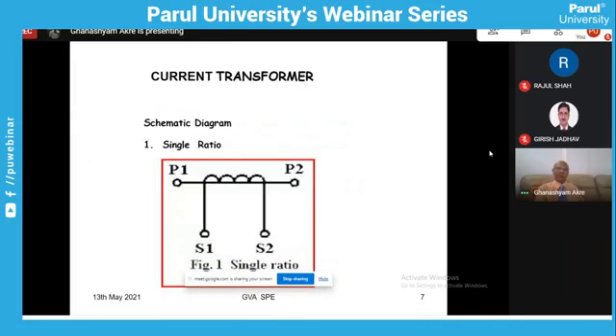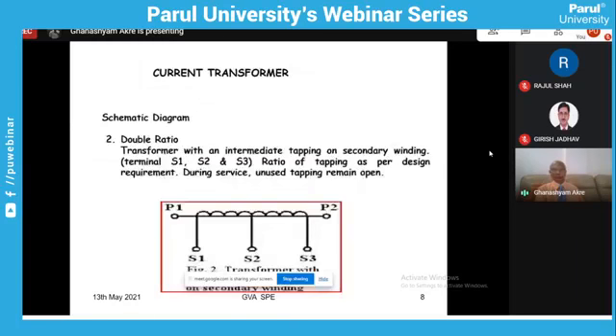This can have either a single ratio, that means P1, P2 and S1, S2. If it is 100 by 1 ampere, it can have only 100 by 1 ampere. So it is a single ratio transformer. Others can have a tap transformer. Here you see 1S1, 1S2 will be 50 by 1 ampere, while S1 and S3 can have 100 by 1 ampere if there are double the turns. So like that, in the same core, you can have two different current ratios.